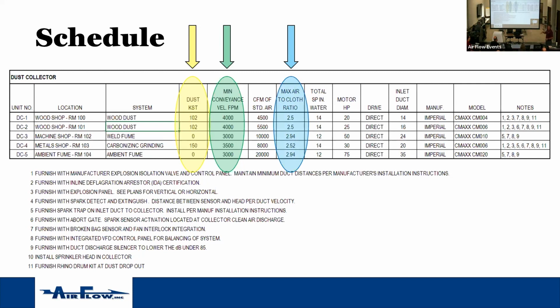Also, the efficiency of a cartridge collector, a shaker, anything that's got media in it, is dictated by what your air to cloth ratio is. So the better your air to cloth ratio, the longer your filter life is going to be. If you go with a less efficient filter and you're trying to put more air through the same square footage of media, you're probably going to have to change your filters more often. But that also gives your customer the ability to say, I'm changing this out in the future, what do I need to do? Here's what we designed it to on the initial side.